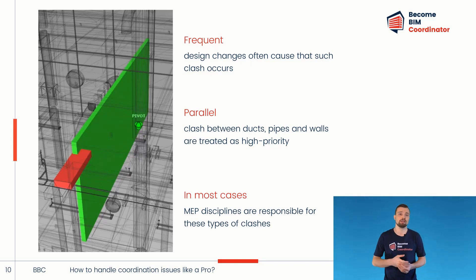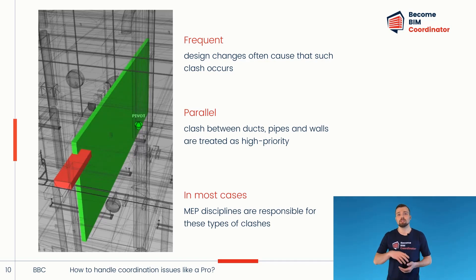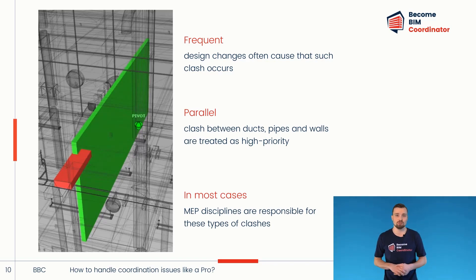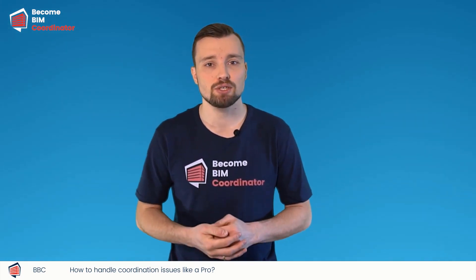The MEP disciplines are responsible for these issues and needs to change the position of the duct so it doesn't collide with the wall. However, when large-sized ducts and pipes collide with partition walls, it may be faster and cheaper to move the lightweight partition wall and leave the duct as is. These individual cases should be discussed internally between disciplines. I have now shown you some examples of clashes that are often considered high priority, selected by the BIM coordinator and presented during coordination meetings.